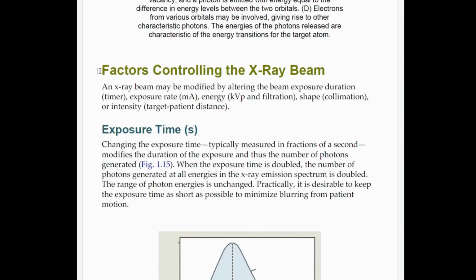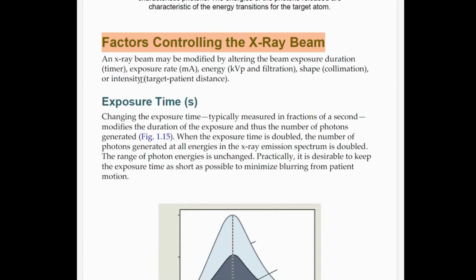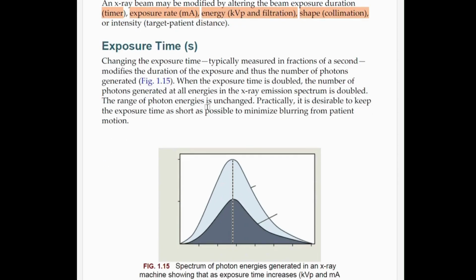Now we move on to the factors controlling the X-ray beam. There are 3 to 4 factors which control the X-ray beam. First is the timer, exposure rate, that is the milliampere current, energy, that is the kilovoltage, shape, that is nothing but collimation, and intensity. So these are the factors that control the X-ray beam. First, we'll start with the exposure time. Changing the exposure time, typically measured in fractions of a second, modifies the duration of the exposure and thus the number of photons generated. When the exposure time is doubled, the number of photons generated at all the energies in the X-ray emission spectrum is doubled.